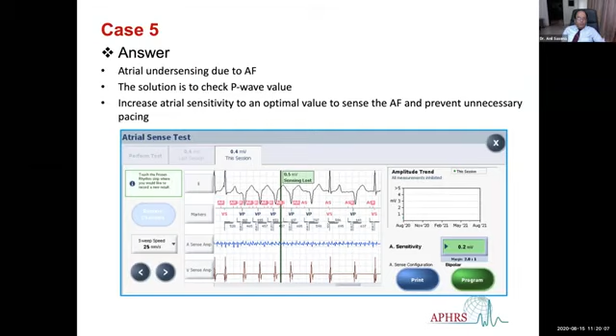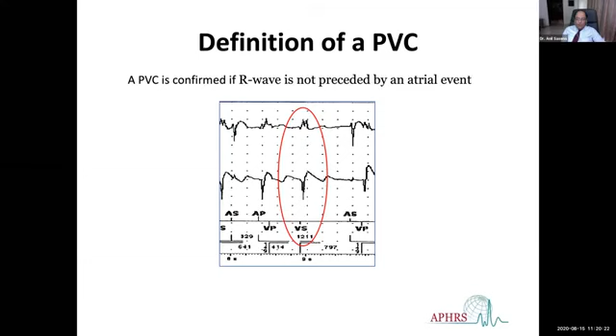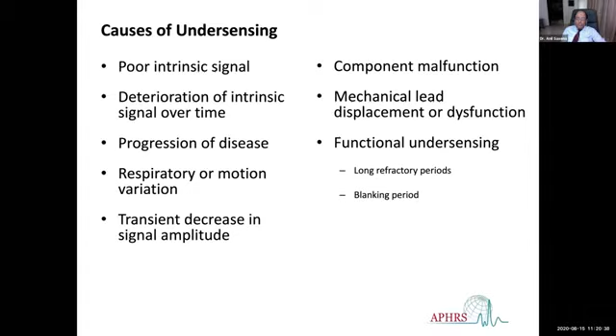So the answer is that it was atrial undersensing because of atrial fibrillation not being sensed, and by increasing the sensitivity we can solve it. And this is the picture showing, which I already mentioned, that if there is a ventricular activity without any preceding A sense or A pace, then it is counted as a PVC. And the cause of undersensing could be poor intrinsic signal, it could be deterioration of the intrinsic signal, it could be component malfunction, it could be some disease process happening in the atrium which has reduced the electrogram amplitude.